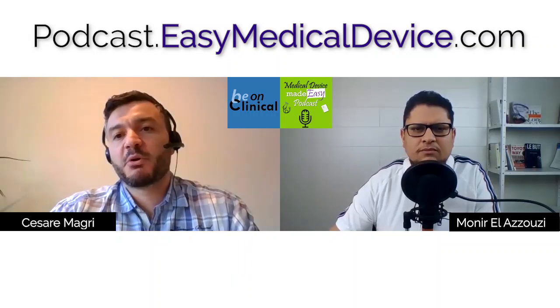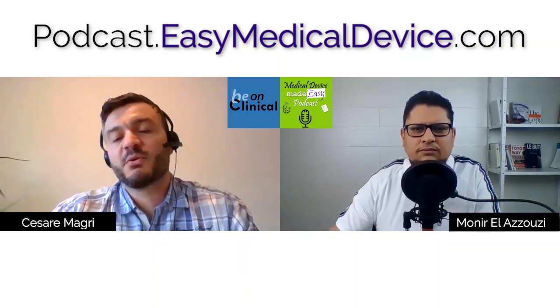The way we structure it is that intended purpose is the general description of the purpose of your device, and the intended use is a part of this intended purpose. So it's the description of how you are meant to use the device. Often the term intended use is also used to describe the whole thing. This distinction between the two terms is not always clear, but if one wants to be 100% precise, one should think that the intended use is just one piece of it, and there are essentially 5 pieces of the intended purpose that one has to take into account, and the intended use is one of them.